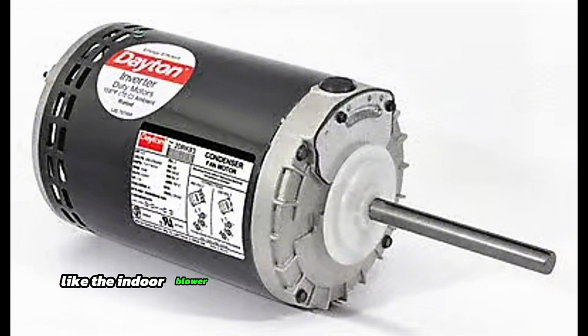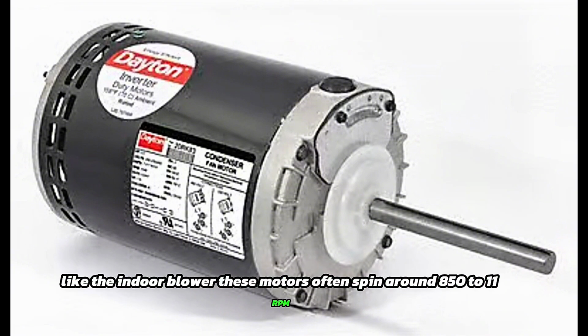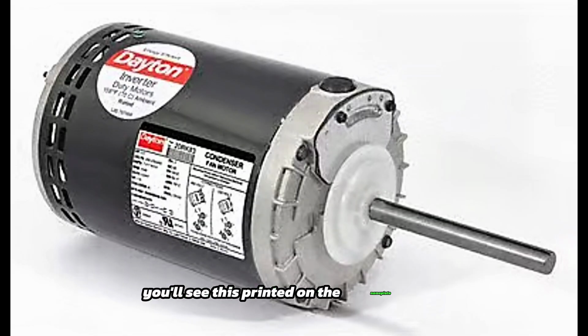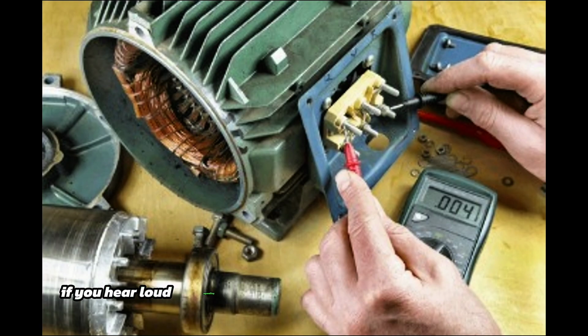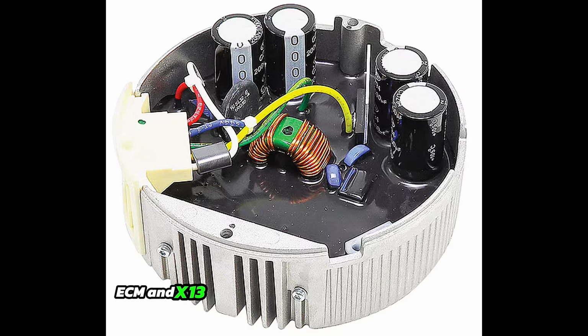Like the indoor blower, these motors often spin around 850 to 1100 RPM. You'll see this printed on the nameplate. If you hear loud squealing or buzzing, or if the motor won't start, check the capacitor first, then the motor windings using your multimeter.